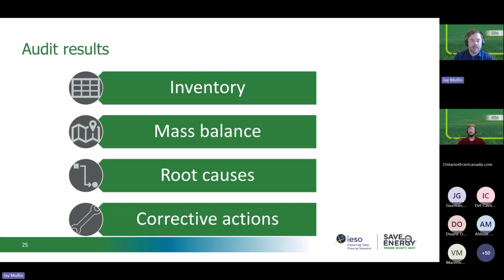So a full inventory. They'll provide a mass balance analysis, so showing airflow in and out of different areas in your facility, indicating which makeup air units should be operating in correlation with specific exhaust units to balance that mass flow within a specific area. This is really useful to indicate those imbalances that are happening by zone. An air balance study should also be pointing to some root causes of that. So a summary of what is contributing to that excess positive or negative pressure. And lastly, some recommendations around corrective actions that can be taken to address and maintain appropriate pressurization.